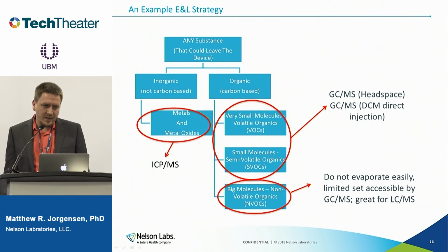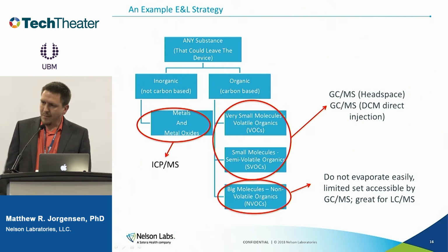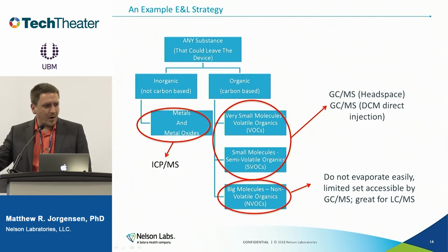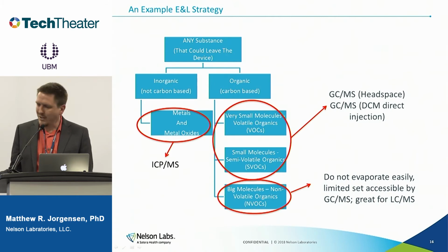If they start to be really heavy, sticky molecules, then GCMS just isn't a good option, because once it gets into the machine, it can't really vaporize, and it just stays in there. You don't see it. So for those, we would use LCMS. There, the molecules stay dissolved in a liquid, the liquid gets carried through the machine, and they are separated that way.